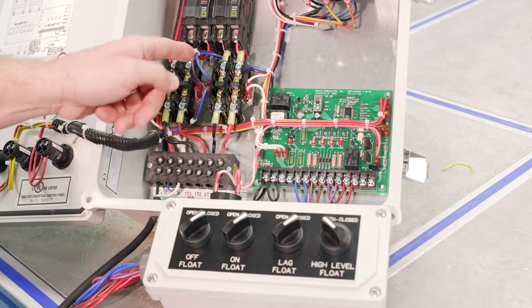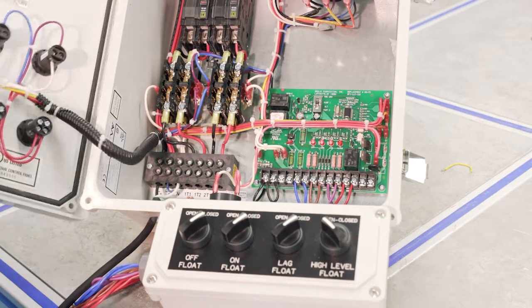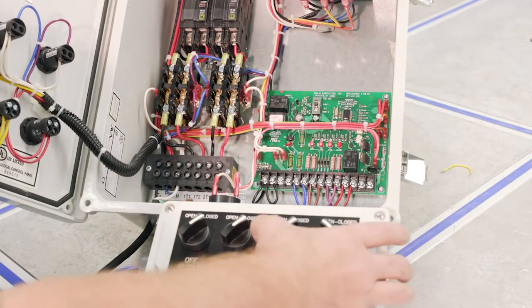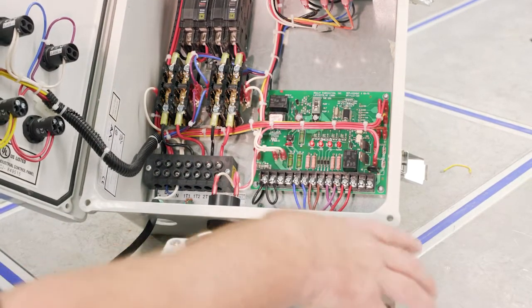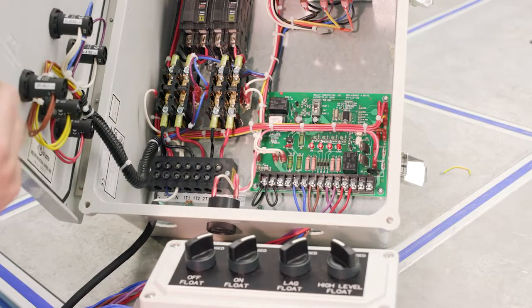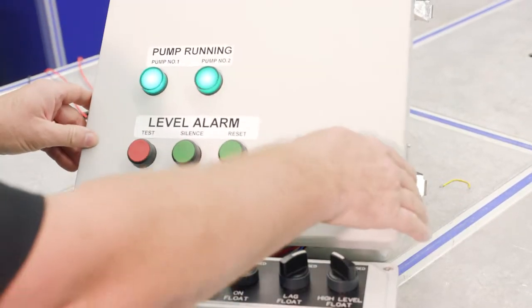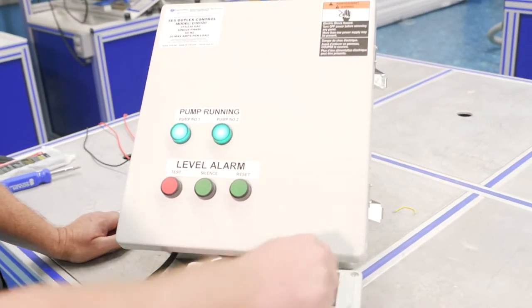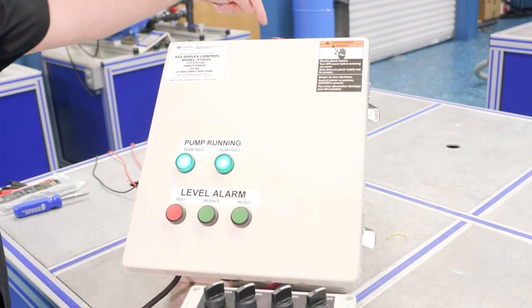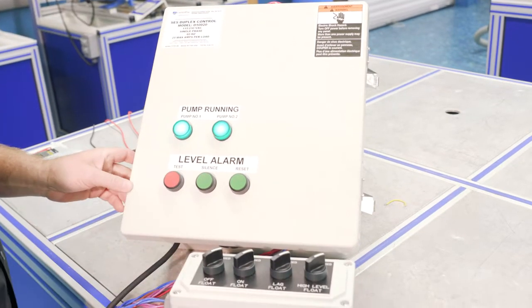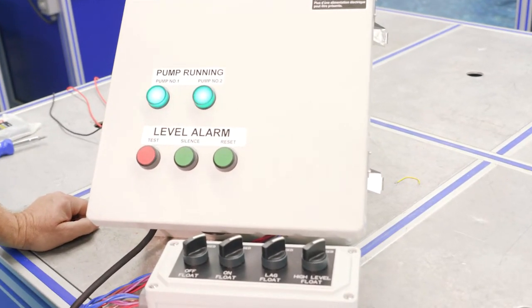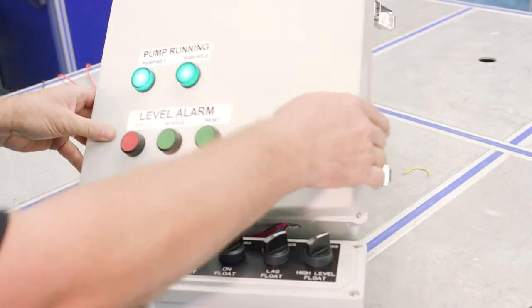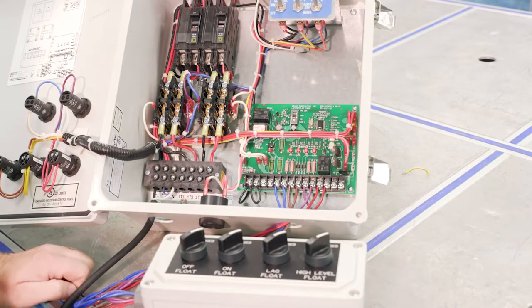Light goes on, contactor pulls in, we've got two pumps running. So in this scenario, the pump still can't keep up. So let's close this for a minute so we can see, and now the high level alarm. Light is on, alarm is on, let's just silence that, and then reset it.